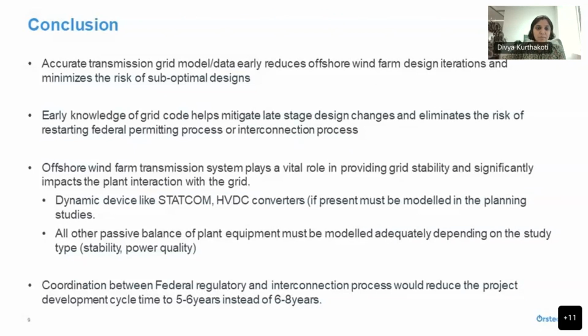Because we make assumptions on grid model or data, assumptions about short circuit, assumptions about harmonics, we have to iterate. If we have this information early on, we minimize suboptimal designs and the number of iterations. One thing we really liked about having a common uniform standard like IEEE 2800 is we know that upfront, so it's easier to design upfront when we start the process. It's very hard to make design changes towards the end of the process.